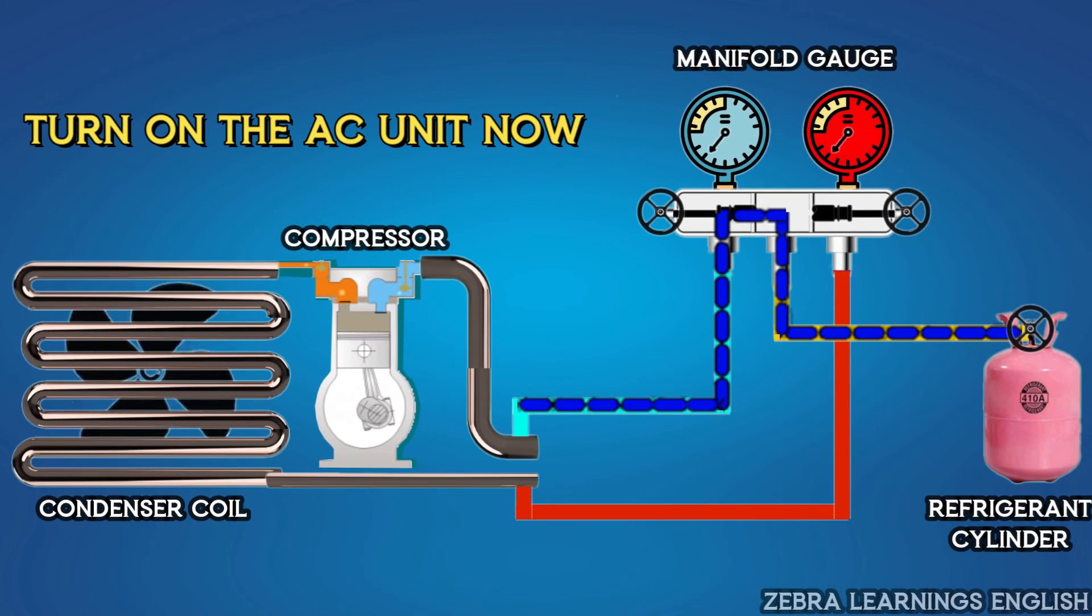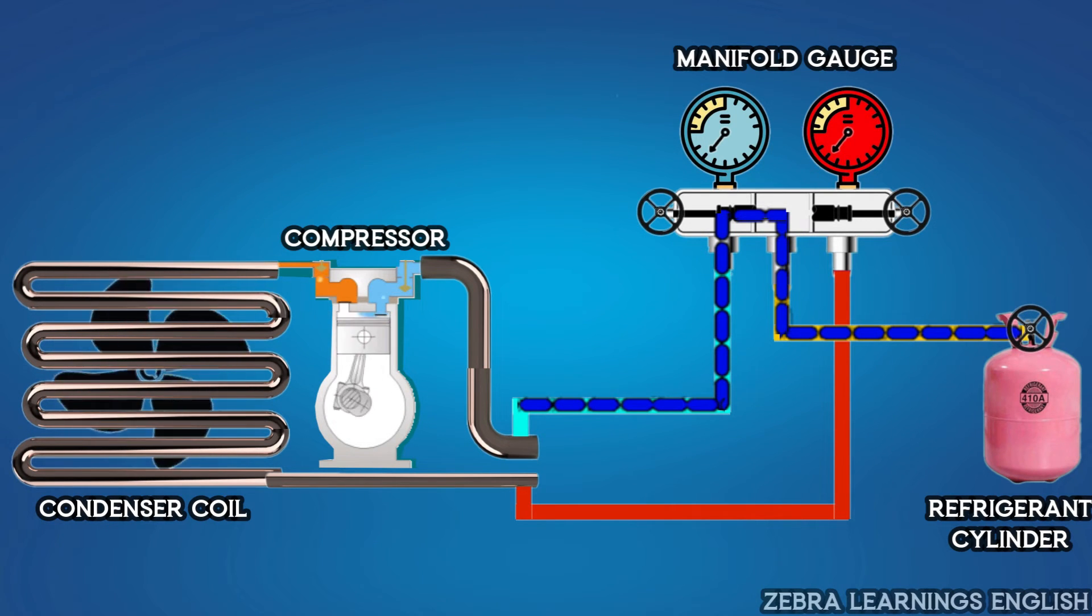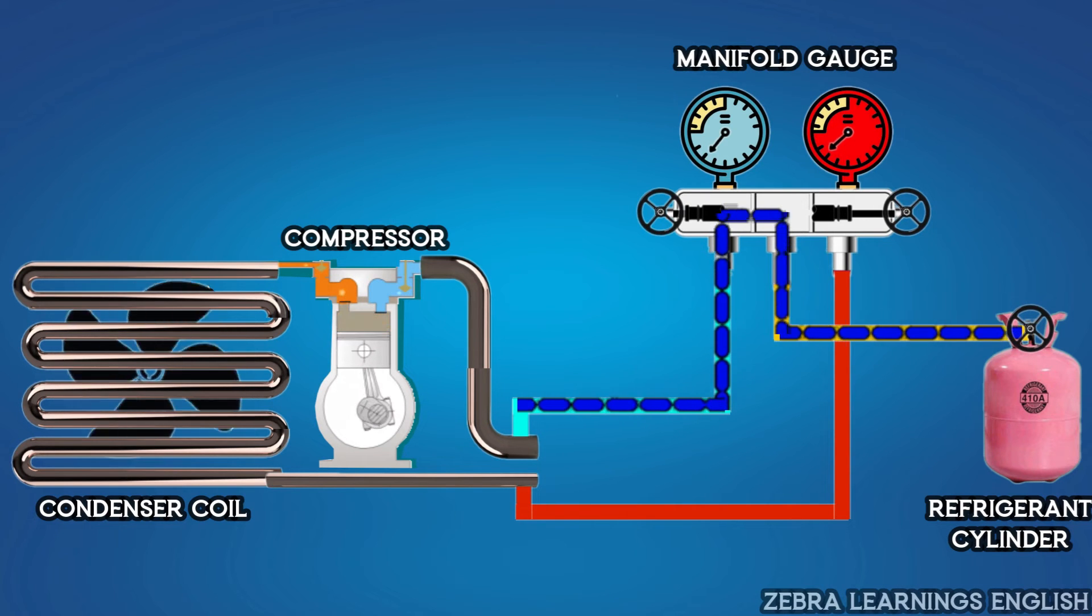Now, we can charge the refrigerant in the unit. First, turn on the unit and open the valve of the refrigerant cylinder. Then, open the low-pressure valve. After opening, refrigerant starts charging from cylinder to suction line. This process should be done only when the unit is running.